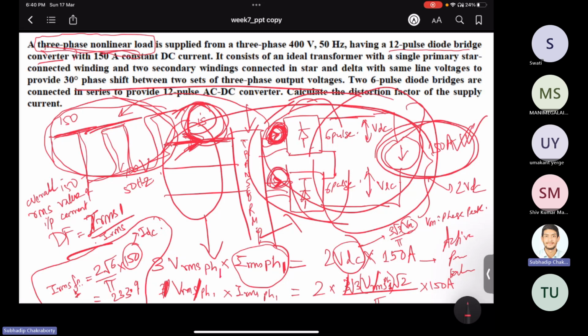But you have to also reflect and then add, right? And all turns ratio you assume same. So once you know the currents of any one of the phases for these two, one is star, so that will go in line with this. But in delta you need to understand that transformations happen phase to phase. So take the phase current of that delta, which is by √3, and then you multiply it with this current. If it is amplitude I, then in delta it is I by √3, whereas this is I only.